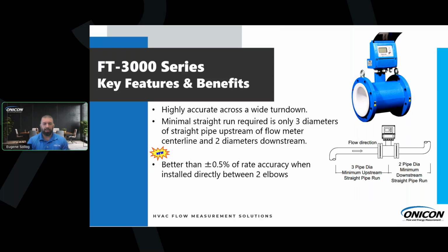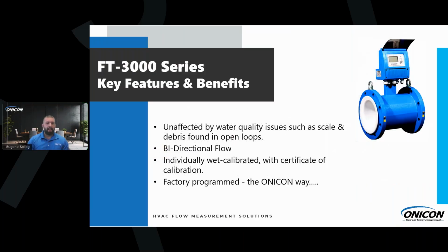Also, a new feature for the inline mag is a 0 straight run requirement, and we still have better than plus or minus 0.5% of rate accuracy when installed directly between 2 elbows, exactly like that picture, without that straight run. The inline mag is also ideal because it is unaffected by water quality issues such as scale and any kind of debris found in open loop water systems, so it's ideal for any kind of who knows what's flowing through these pipes.